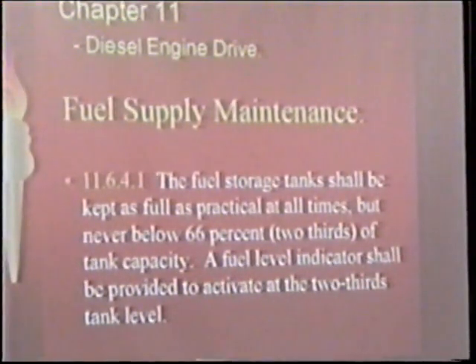I don't know. Normally we just wire that right back to the controller, and then the controller sends it out. I've always recommended that it be sent as a separate point. In Firetrol, we have the contact outputs to make it a separate point. I've always recommended it be used that way because they don't need to send somebody to the room if they know they've got to call a fuel delivery truck.